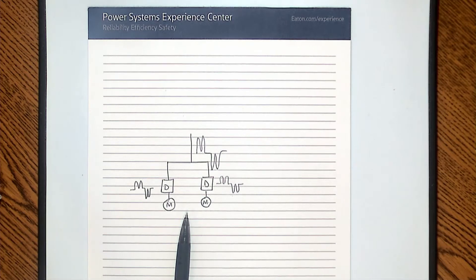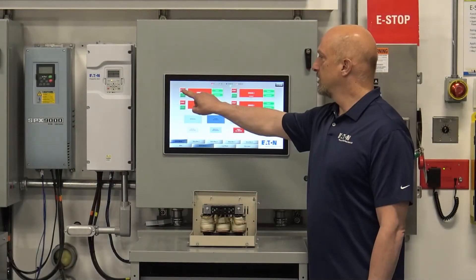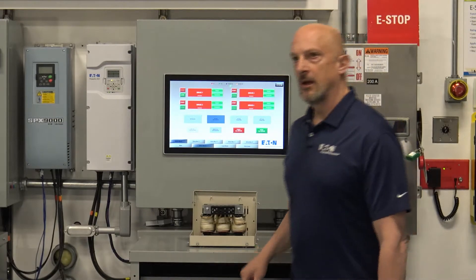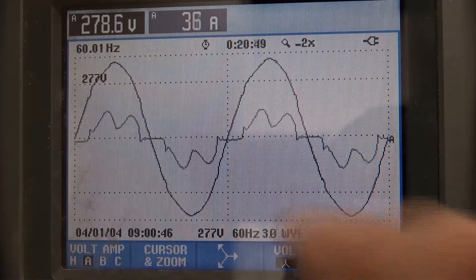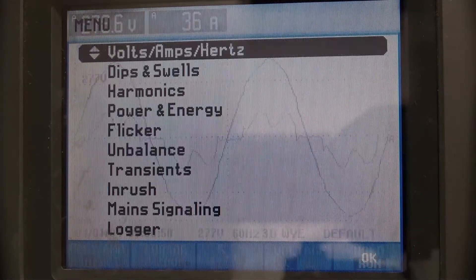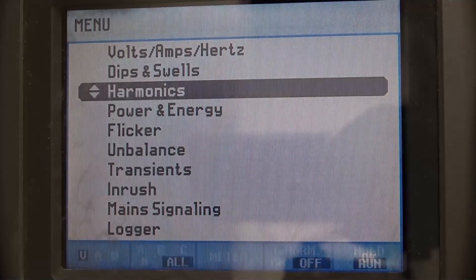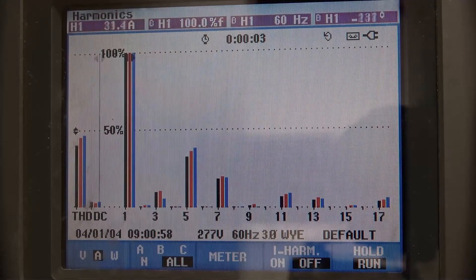We're going to go to a part of the system over here where we're actually going to show you how that works and actually combine these harmonics from drives. We're going to put two different drives on and show how those harmonics add up together. So we'll turn one on, we'll take a look at the waveform, and you can see the harmonics coming out of one of the drives. Now if we take a look at the harmonic spectrum, it shows the typical fifth and seventh harmonics — what you'd expect.